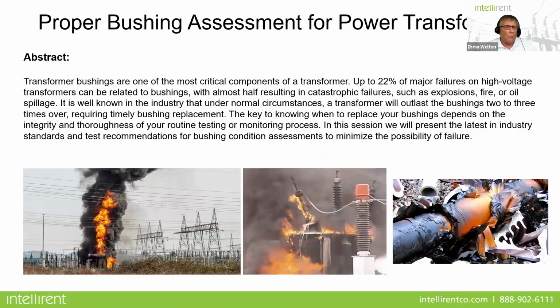Yeah, today we want to talk about a proper bushing assessment for power transformers, and I think as most of you are familiar, the bushings are the most critical components of your transformer, or one of the most, and we see up to about 22% of the major failures on high voltage transformers related to bushing failure. And of those, about half result in catastrophic failures.